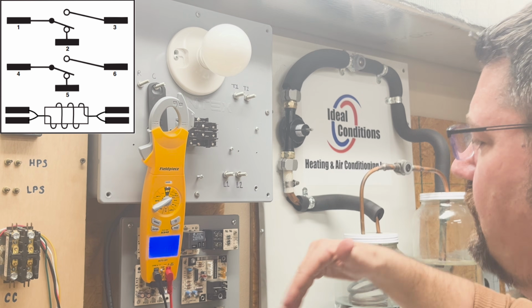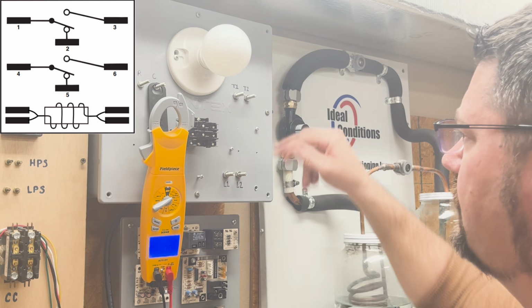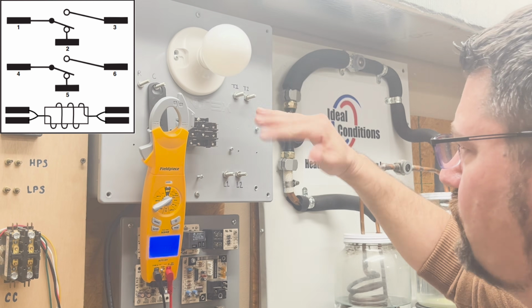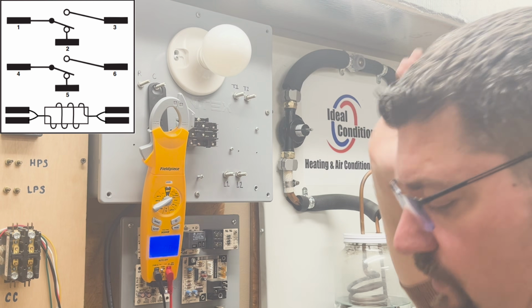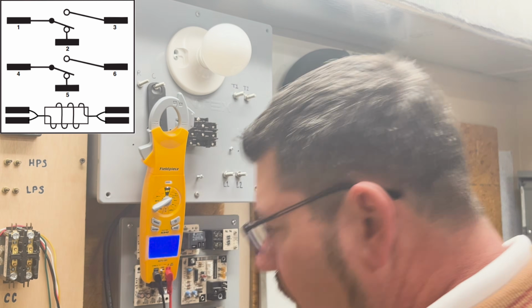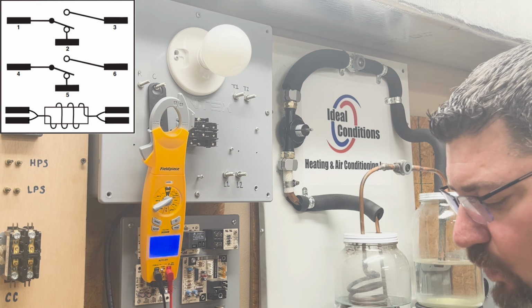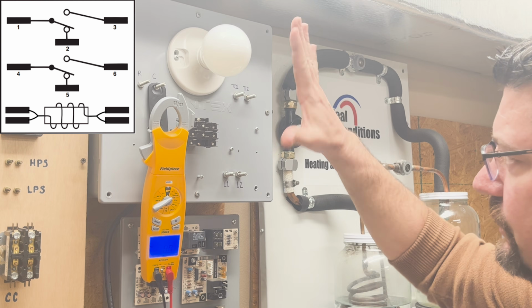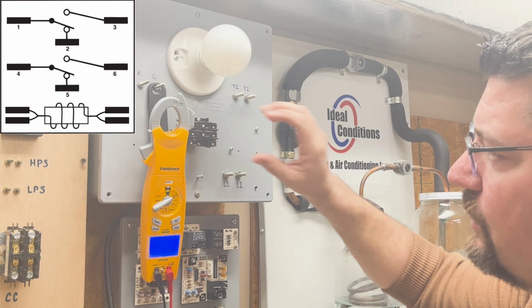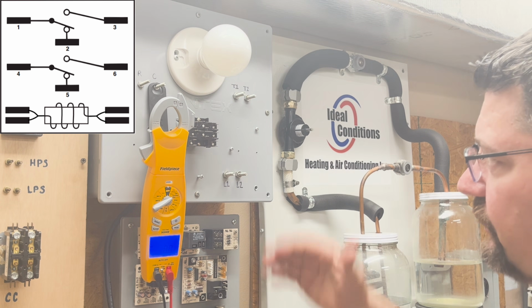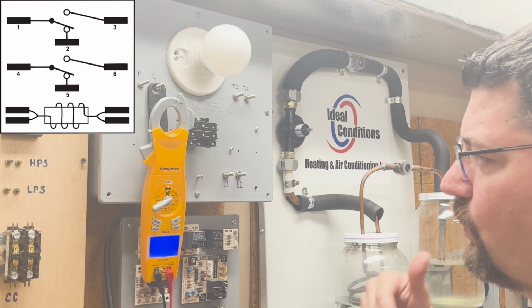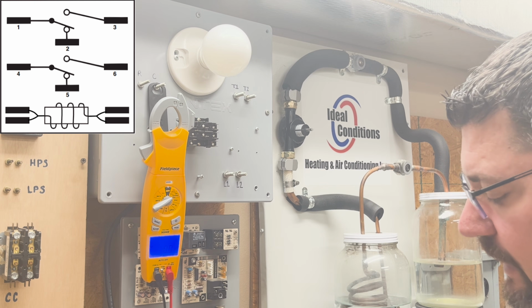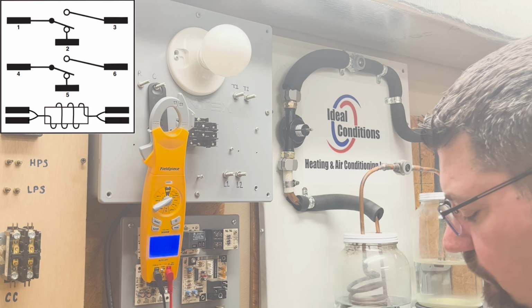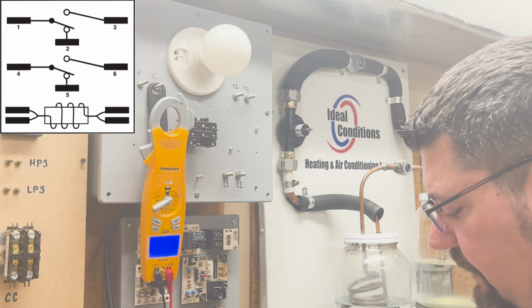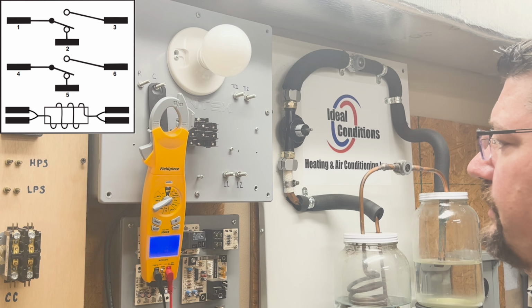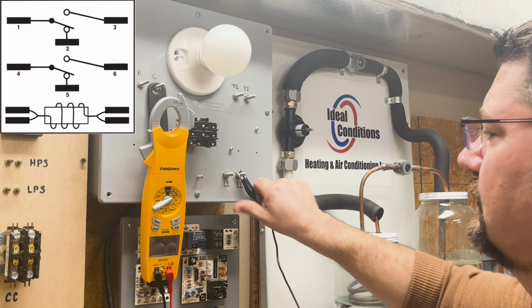With that, we can go ahead and introduce L1 and L2 up here so we can see that if I remove any one of those combinations, L1 or L2, our load turns off. Now in the real world, we're only breaking one leg of power. That's why it's important to show you how to get this load to come on without a light bulb. This load can represent a 240 fan motor, a 240 compressor, or a set of heat strips - it doesn't matter.